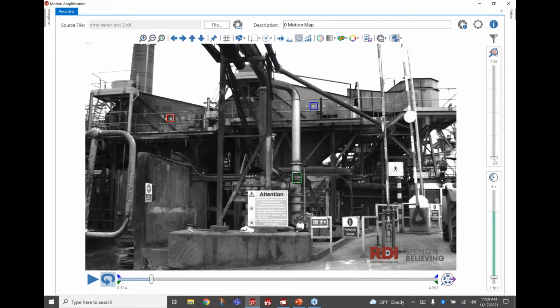That's also some of the beauty of motion amplification technology: if you're using a contact sensor, you get a waveform at a location, but in the video you can often see the source, where the vibrations are occurring, because you get such a big field of view. Often you see, oh wow, I didn't know that was vibrating, and that was actually inducing or causing it. For example, you see a motor rocking, but you don't realize the floor is rocking too, from looseness in the structure underneath. So yes, often you can see the source, and it's one of the benefits.